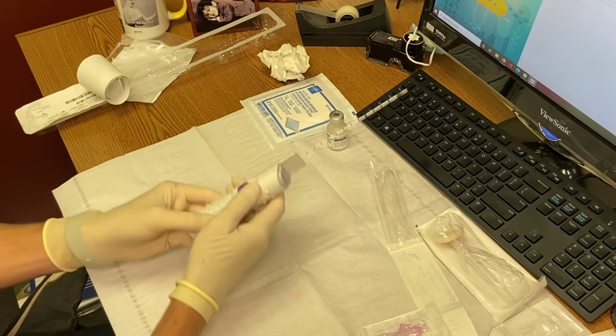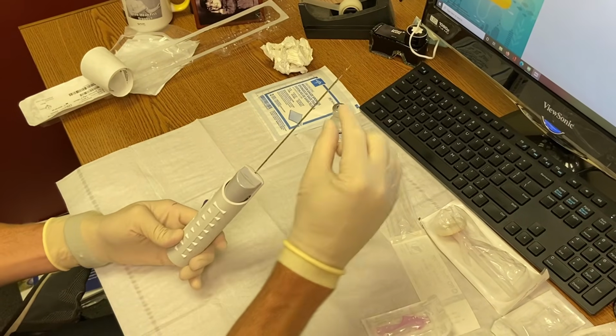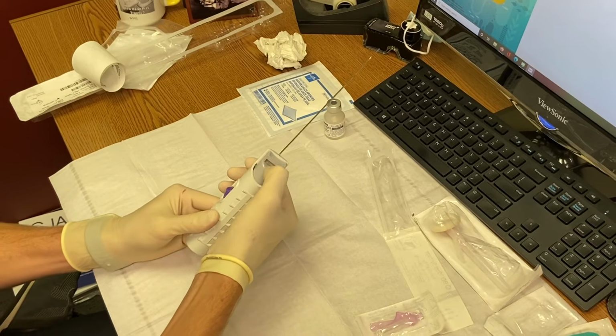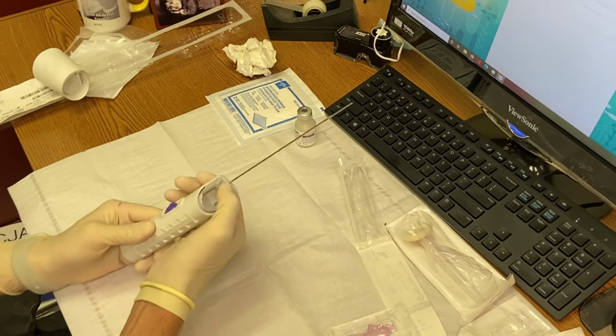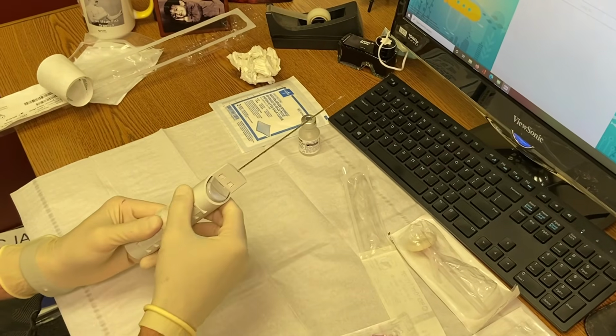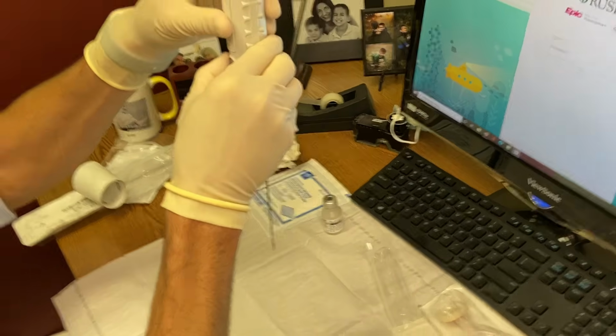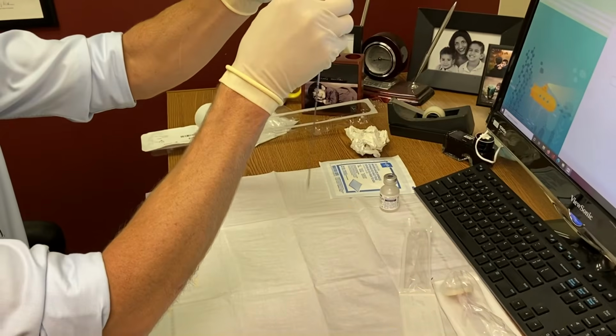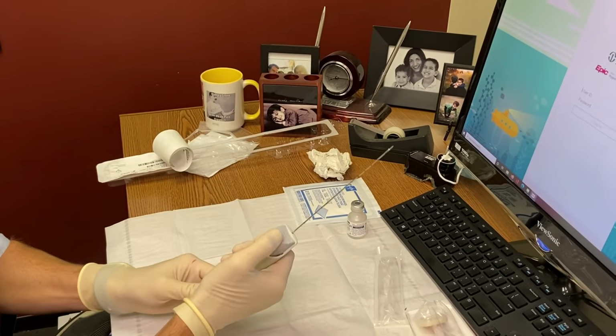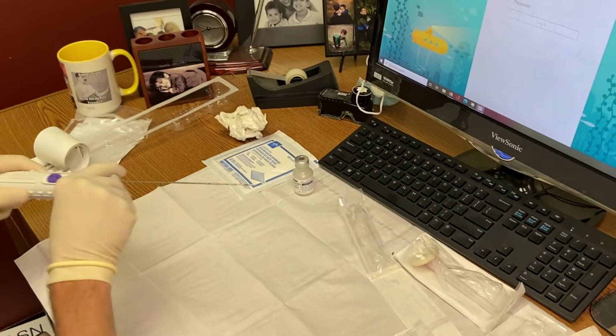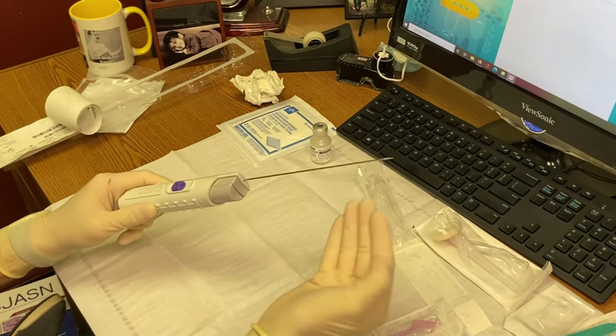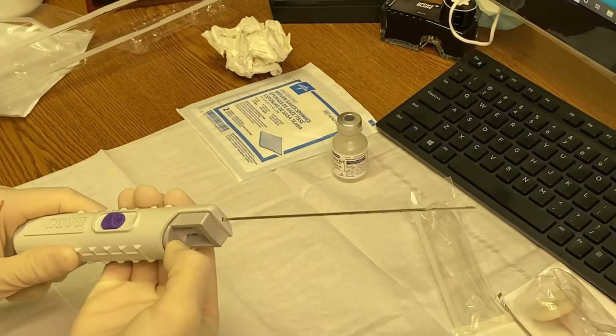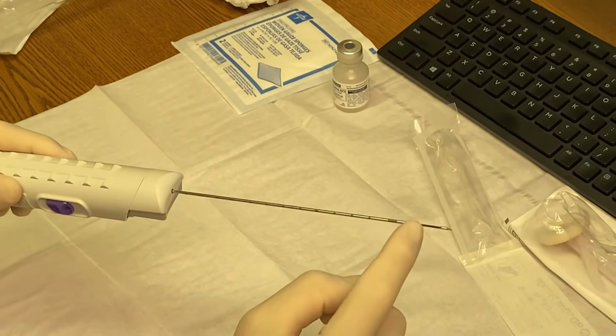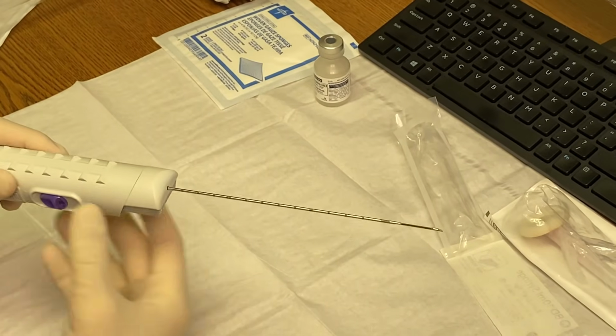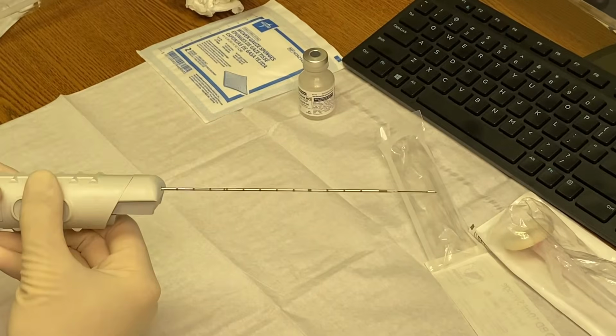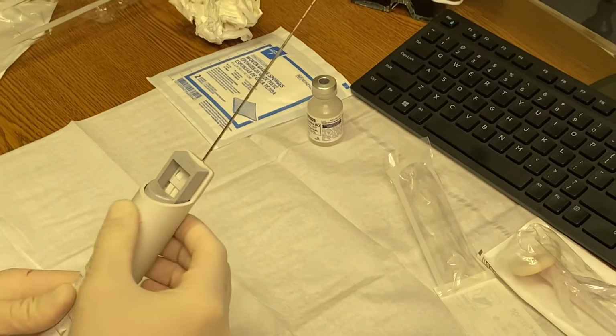So this can be fired by releasing that mechanism, which then allowed it to go up another 2 to 3 centimeters, and then pull back one to expose the external sheath, and the second one to do it again. And you can see it's the same way if you push this button, and that allows the spring-loaded mechanism to exist. So once you pull out and you have kidney on the inside there, the way to give this tissue to the pathologist is to just push down the first button here. And you can see now that there's the hollow core. The piece of kidney should hopefully be there, and you'll allow that to roll off the needle so that you can give that to the pathology technician who's in the room.